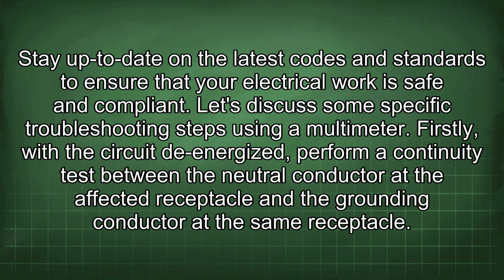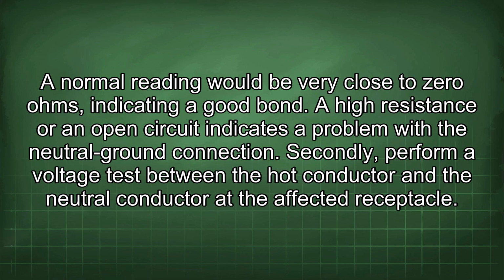Let's discuss some specific troubleshooting steps using a multimeter. Firstly, with the circuit de-energized, perform a continuity test between the neutral conductor at the affected receptacle and the grounding conductor at the same receptacle. A normal reading would be very close to 0 ohms, indicating a good bond. A high resistance or an open circuit indicates a problem with the neutral ground connection.